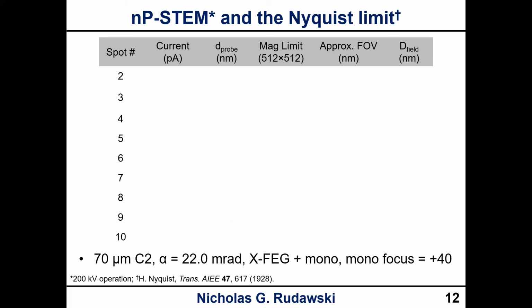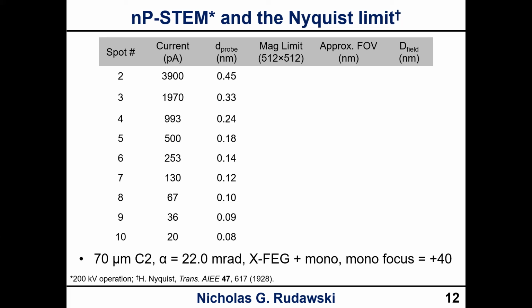We do the same thing with nanoprobe mode, and we see the same behavior with spot size. As the spot number goes up, the current goes down. We can do the same thing with the probe size. But what's really interesting here is that all the way up to about 1 nanoamp of current, around spot 4, we can still get atomic resolution. That's a 2 angstrom probe, and that should be capable of giving you atomic resolution. So you'd have to exceed a nanoamp of current before you start to run into a potential problem there.